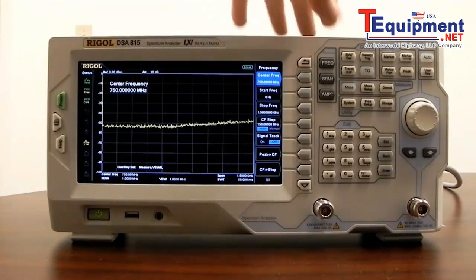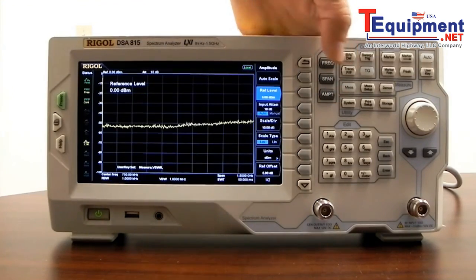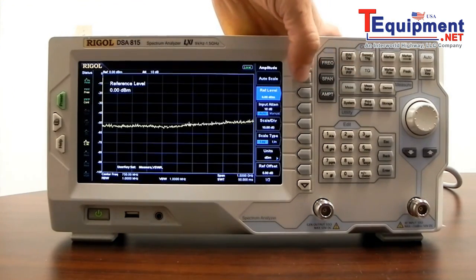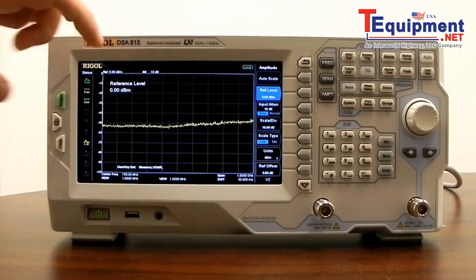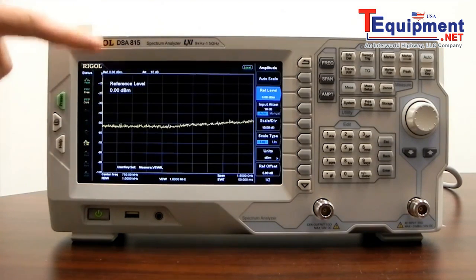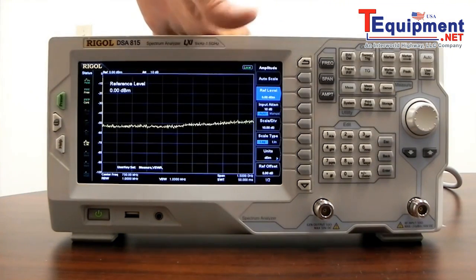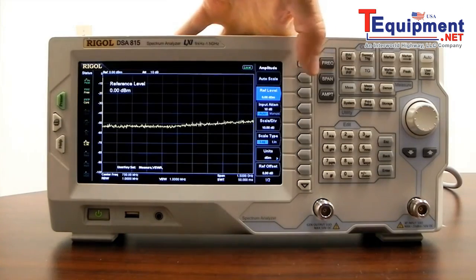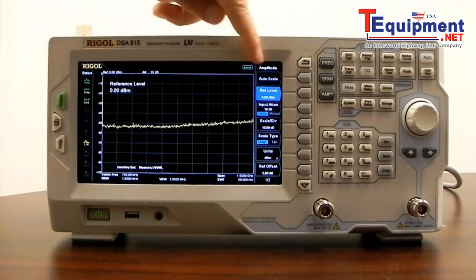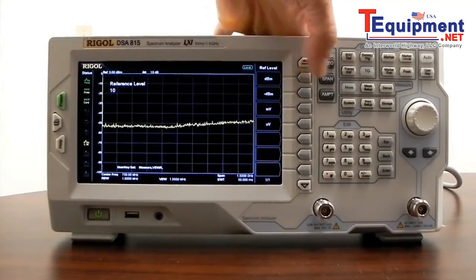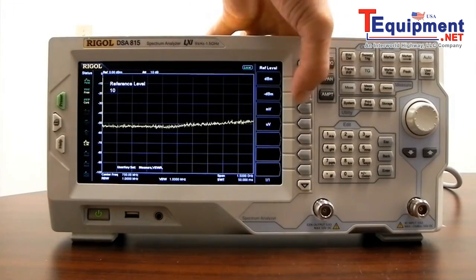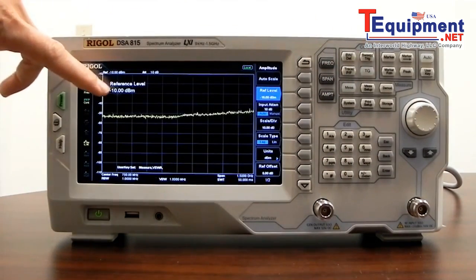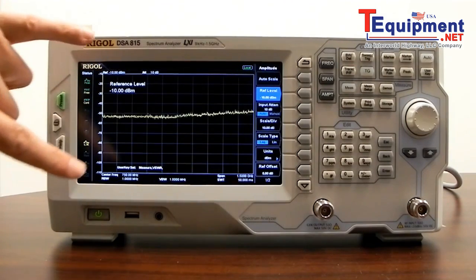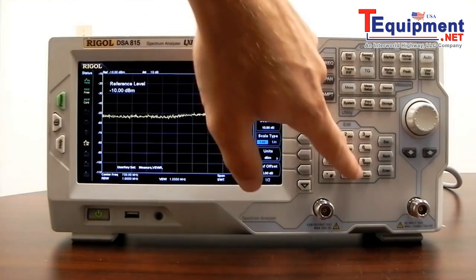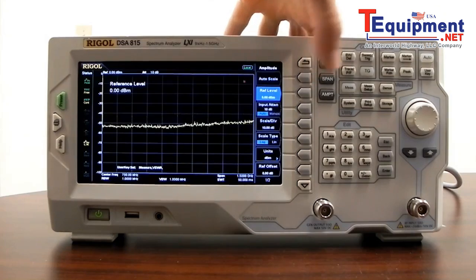Now let's take a look at the amplitude menu. Under the amplitude menu, we've got auto scale, which is going to adjust the scale, the values of each of the divisions, to match the incoming input. We have reference level. Again, reference level is that top line. So if we wanted to go to minus 10 dBm, we could press 10 on the keypad and press minus dBm, and now you'll note that it says reference level minus 10 dBm. So basically it moves that whole window up. Let's go back to 0.